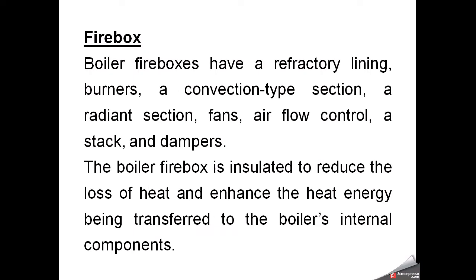The firebox is a component which is comprised of refractory lining. It has a burner, a convection-type section, and a radiant section for heat radiation and convection. It also includes fans for the flowing of air and fuel, air control, a stack, and dampers. The boiler firebox is insulated via refractory lining or refractory bricks to reduce heat loss and enhance heat energy transferred to the boiler's internal components.